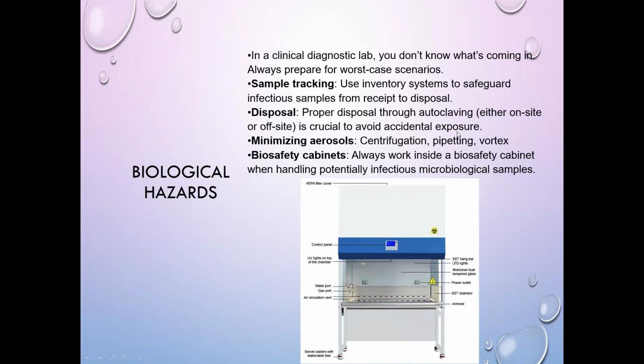We need to have a way to minimize aerosols because aerosols can be formed through using centrifuges, through pipetting or vortexing samples. And if we are vortexing samples, one of those times that comes to mind when COVID first hit, the very first samples required us to vortex samples that had actual COVID in it with the reagent material. And so we had to wear those N95s to prevent ourselves from getting sick by those aerosols. A good way also to prevent ourselves from having aerosol contamination is by using biosafety cabinets properly. Now, if we are using biosafety cabinets, we do need to make sure that those are actually getting maintained properly. They should be being checked every single year to make sure that they are functioning correctly.